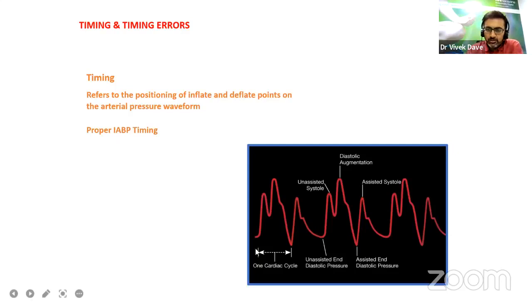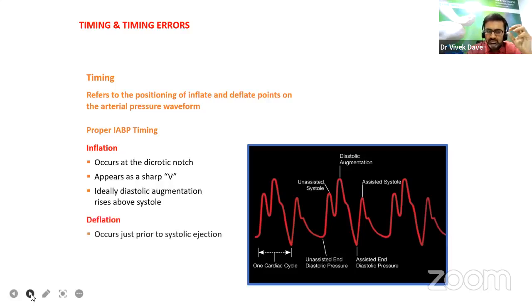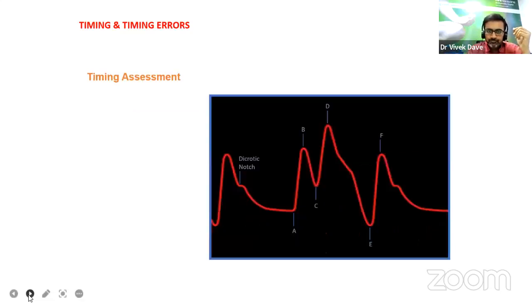This is the waveform of IABP. This is one cardiac cycle — unassisted end-diastolic pressure, unassisted systole, and diastolic augmentation. Timing is very, very important. It refers to the position of inflate and deflate points on the arterial pressure waveform. Inflation occurs at the dicrotic notch and appears as a sharp V. Ideally, diastolic augmentation rises above systole. Deflation occurs just prior to systolic ejection and results in a reduction in assisted end-diastolic pressure and assisted systolic pressure.